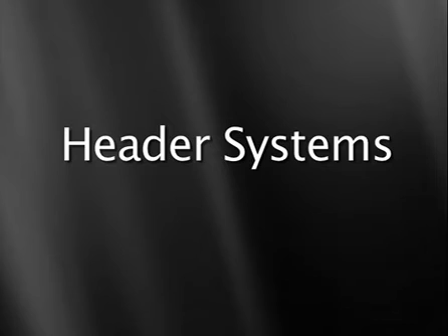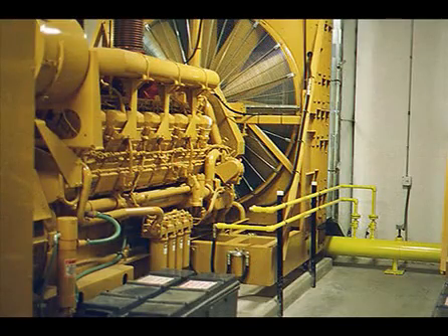Another method for providing day tank protection is an overflow receiver and pump unit. The overflow receiver may be used to accept overflow from a group of individual day tanks. A header system is a response to fuel quantity limits for multi-generator applications. The header pipe is an 8 to 12 inch diameter pipe that runs the length of the generator installation. It acts as a common day tank for all generators with supply and return connections. The header pipe has a gravity overflow return to the fuel supply tank to maintain atmospheric pressure for the fuel supply. Pump controls operate to continually circulate fuel when generators are active.